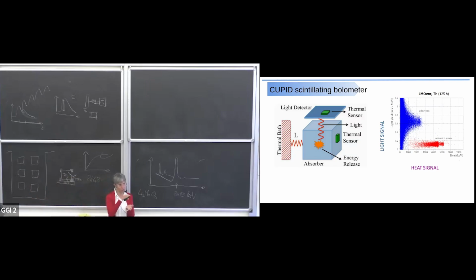So we have a vacuum in between the crystal and the light detector. And this is a big problem, because the efficiency with which the photons can go out from the crystal and enter the light detector is much lower, because the refractive index of the crystal and that of germanium is high, and the refractive index of vacuum is 1. And that's it.